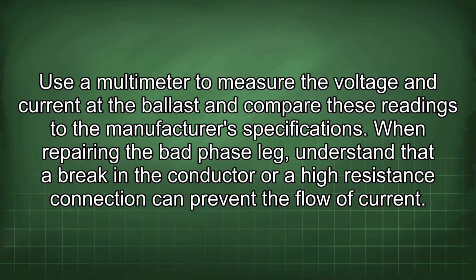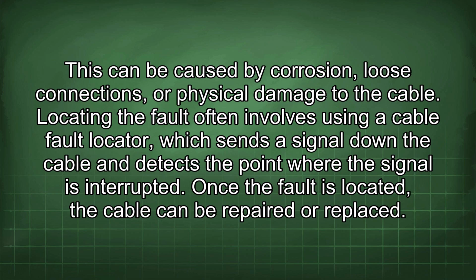When repairing the bad phase leg, understand that a break in the conductor or a high resistance connection can prevent the flow of current. This can be caused by corrosion, loose connections, or physical damage to the cable. Locating the fault often involves using a cable fault locator, which sends a signal down the cable and detects the point where the signal is interrupted. Once the fault is located, the cable can be repaired or replaced.